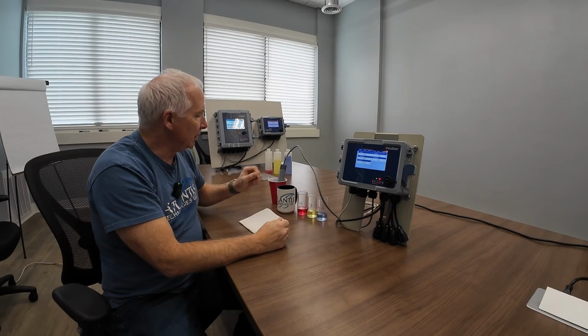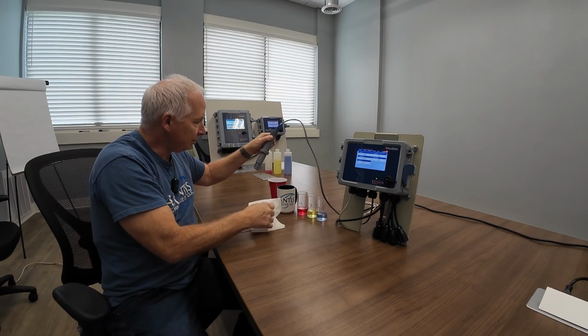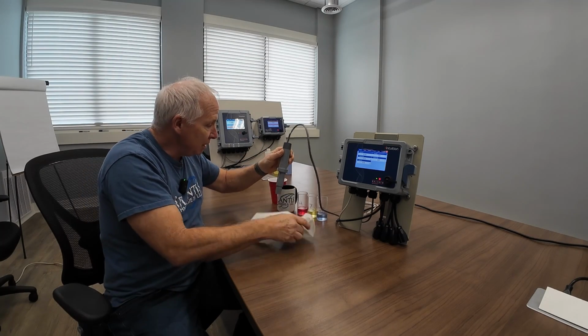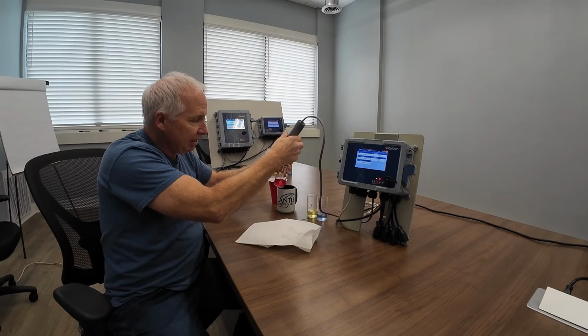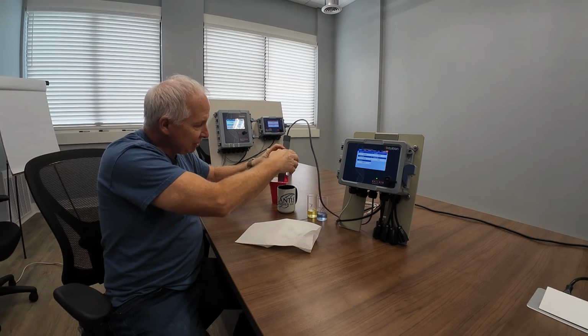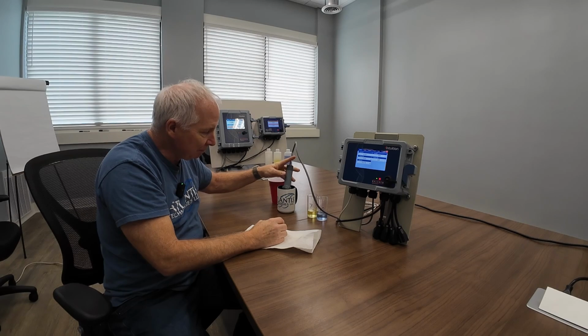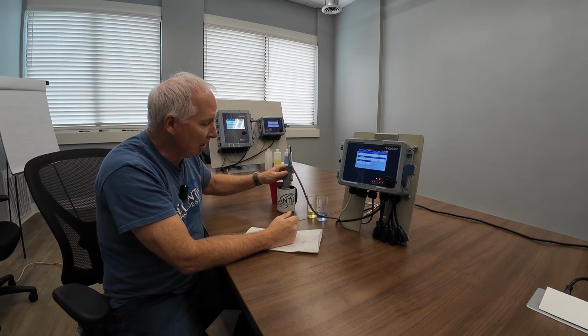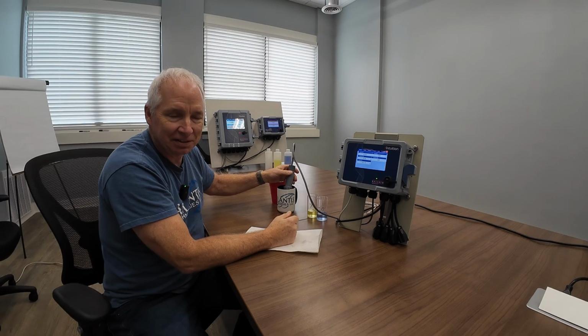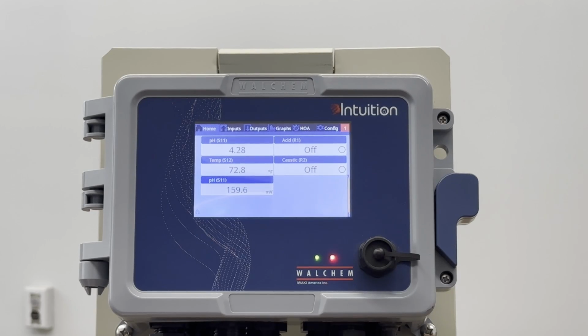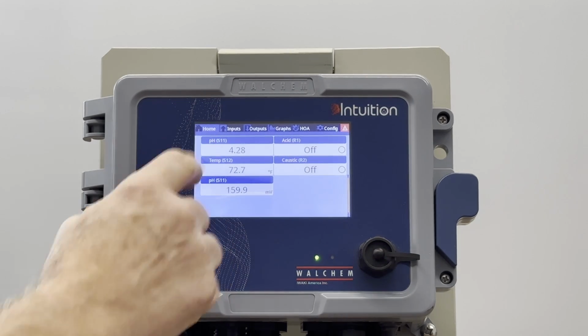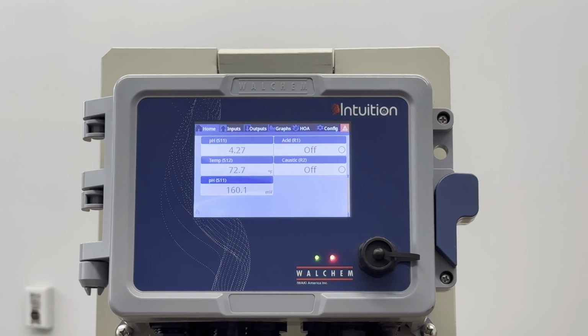The next thing I'm going to do is take my sensor, wipe it off, and put it in the pH 4 buffer. Just to support it, I'm putting it in this cup so I don't have to hold it the entire time. I generally wait and watch for the reading to stabilize before I start my calibration. It just makes it simpler because this isn't an instantaneous thing. As you can see, it's dropping right now on the screen. We're somewhere around 4.27. It seems to be pretty stable at this point.